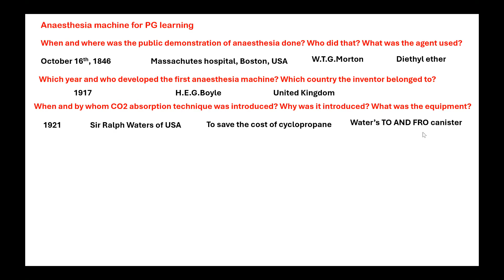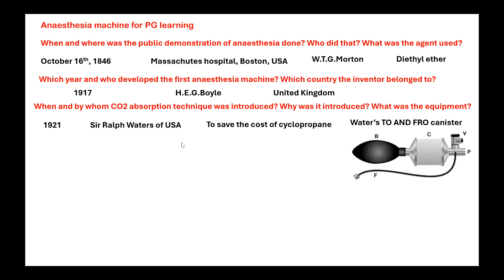If you have not seen it, this is the Waters to-and-fro canister. It is called to-and-fro because gases go in both directions. When the patient is exhaling, the gas goes through the canister with the soda lime, and all the carbon dioxide gets absorbed. It reaches the reservoir back here, and the fresh gas flow comes here from the machine. So when the patient takes the next breath, fresh gas as well as the exhaled gas without carbon dioxide both go to the patient. Because the gas travels in both directions, it is called the Waters to-and-fro canister. And this was the first carbon dioxide absorption technique used in the history of anesthesia.